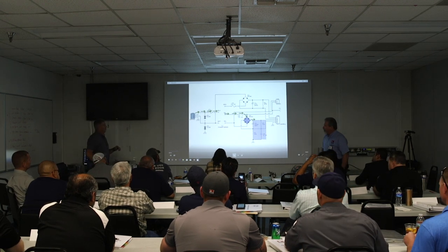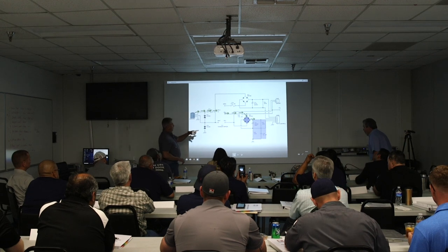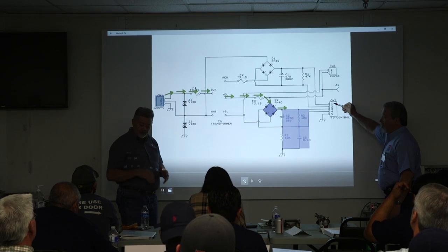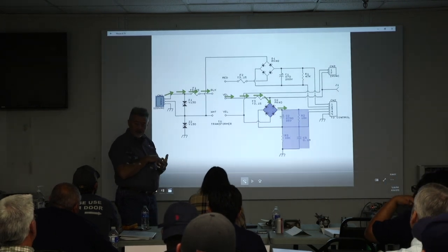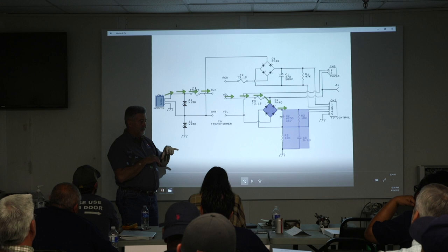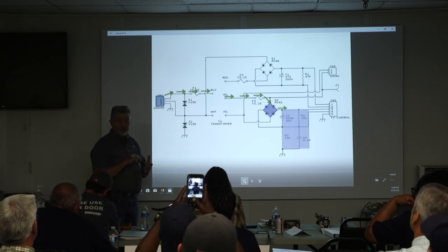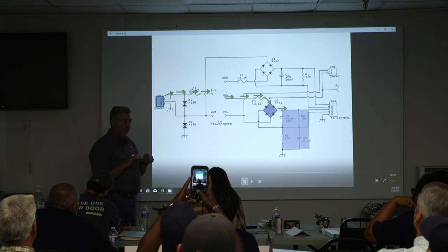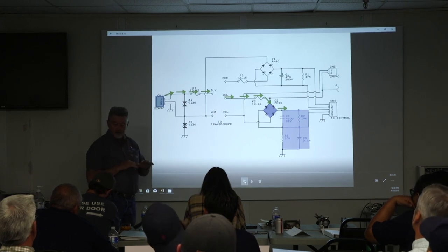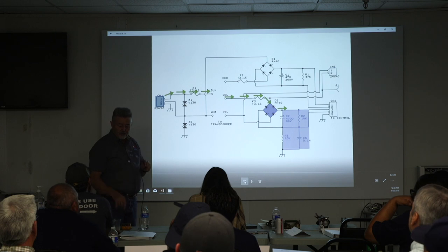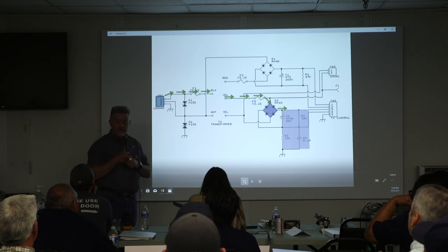Okay. Yeah, and when you're checking that, when you go right over to the plug, 1, 2, 3, 4, 5, those wires, in the video it's showing you to unplug it. You don't have to disconnect it. Leave everything in there and run your probes right through the back of the plug and look that way. Don't disconnect anything. Because it was working previously, so don't start taking it apart. Just use your meter. And like Jim said, you better have your book. You're gonna call him.